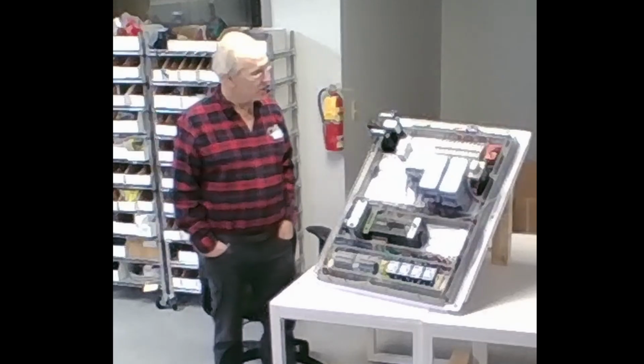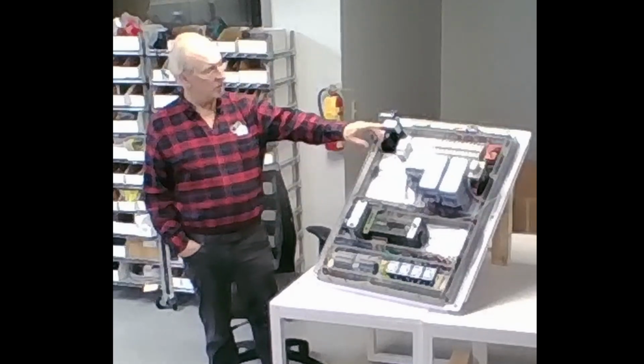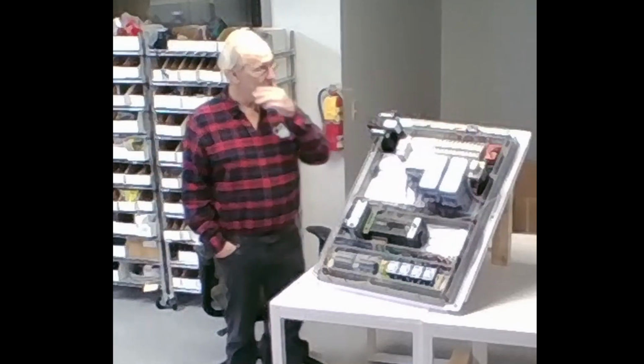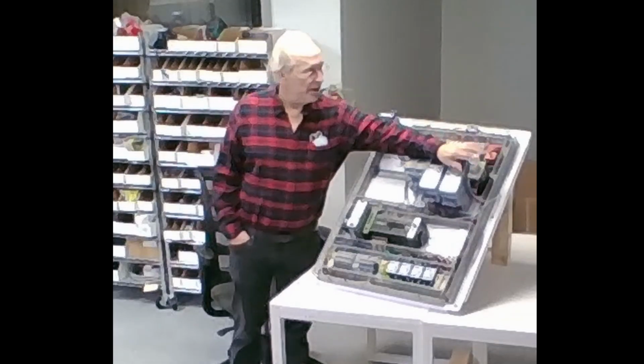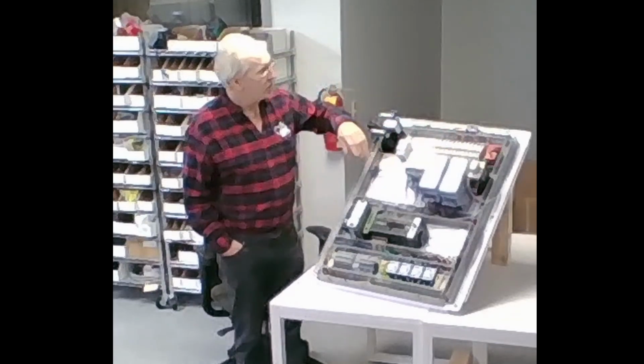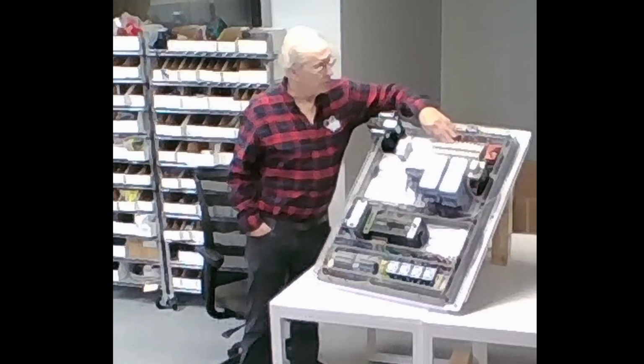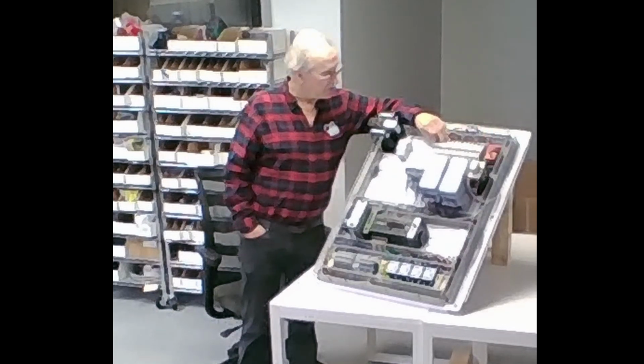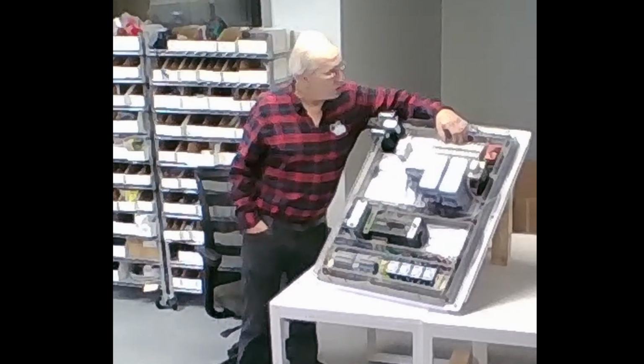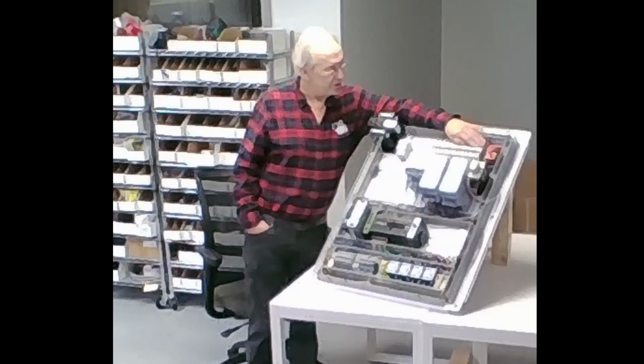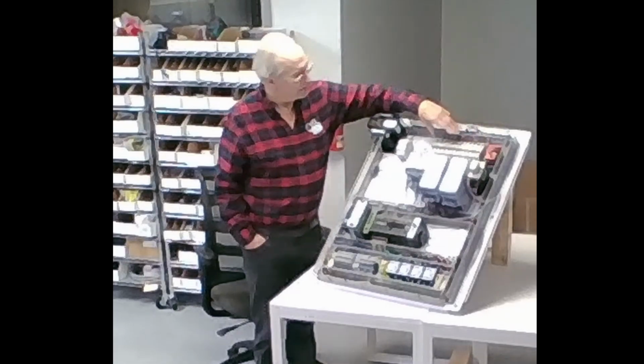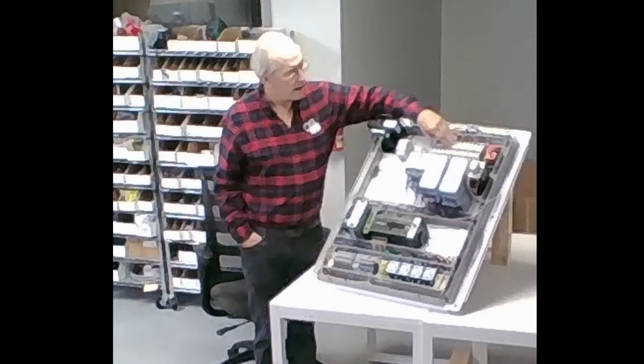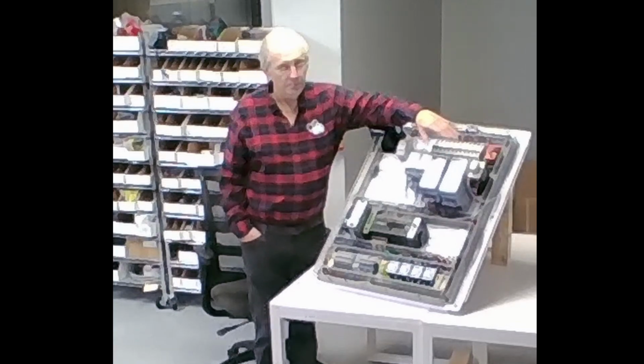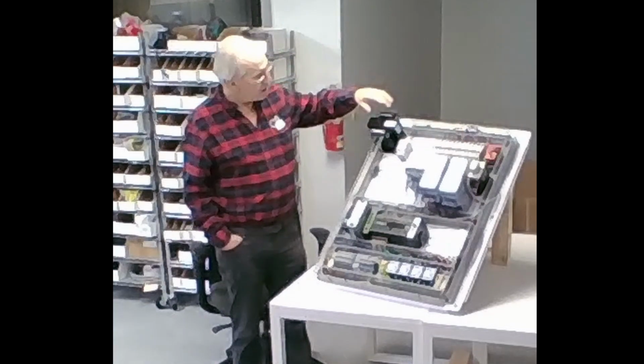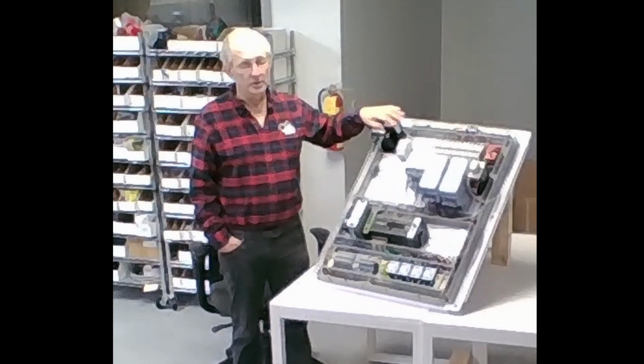Okay, and so like I said, every panel we build, we will have a main contactor, a main switch. So then from the main contactor, we actually go up to circuit breakers to supply power to various things. Now, these are all 3-pole circuit breakers because these are supplying 240 volt 3-phase power to motor equipment. And then we also have a transformer, okay?